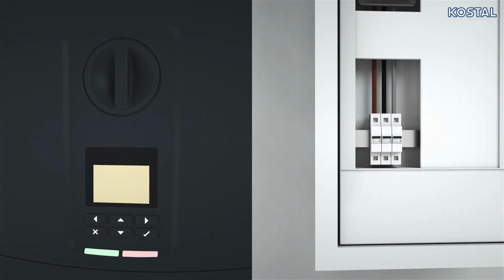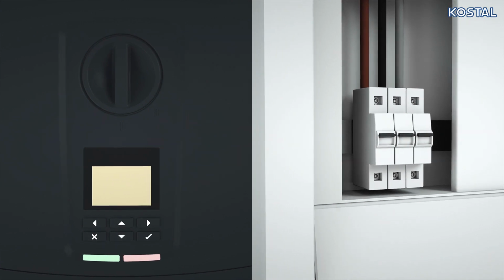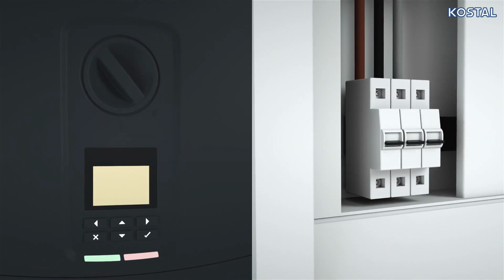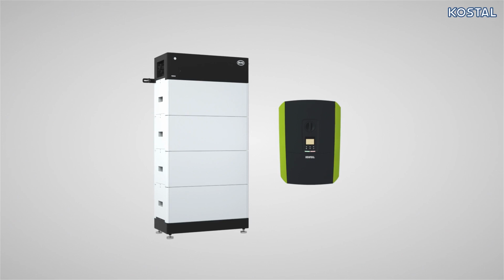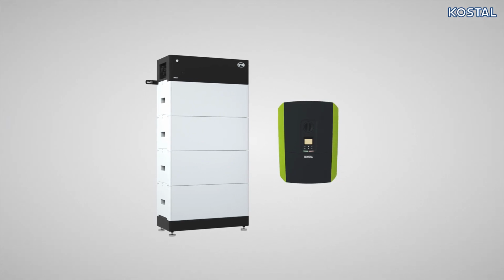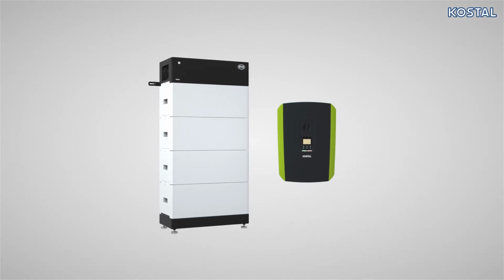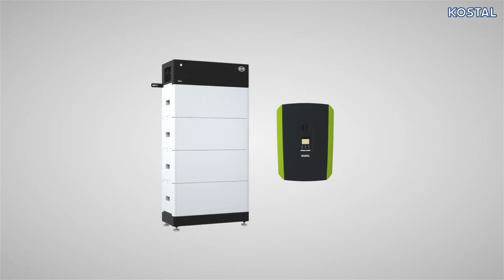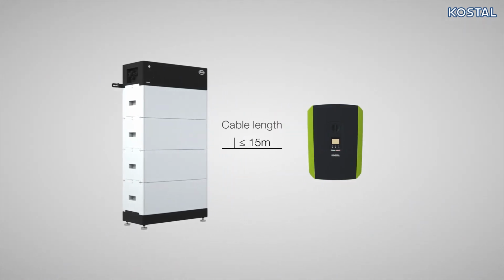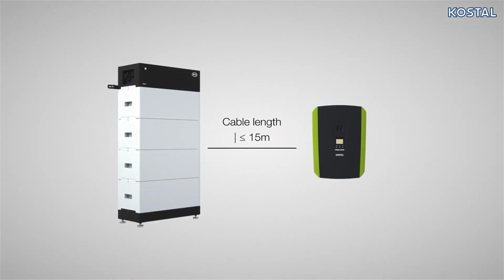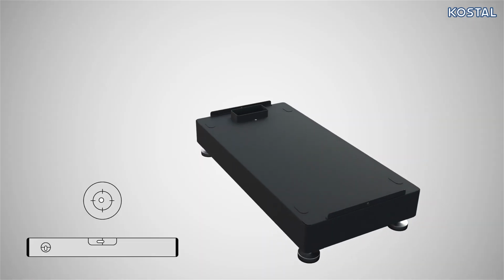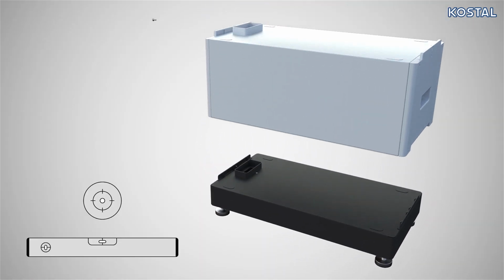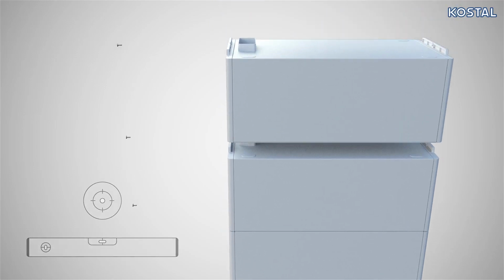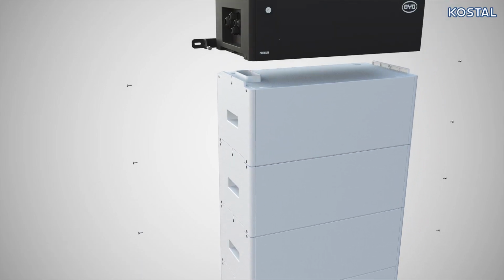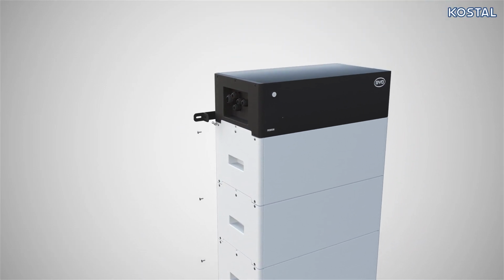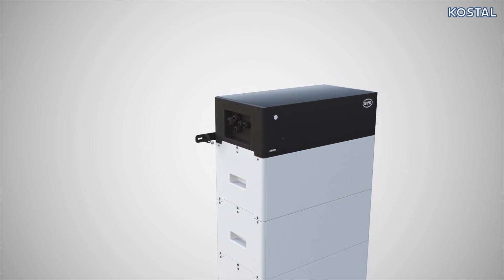Before getting started, switch off any components in your PV system that may already be running. Please install the battery system as outlined in the enclosed installation instructions. Note that the length of the cables between the battery and the PLENTICORE must not exceed 15 meters. First, align the base plate and position the individual battery modules in relation to one another. Finish with the management module, BCU. Screw the modules firmly to one another and the wall.